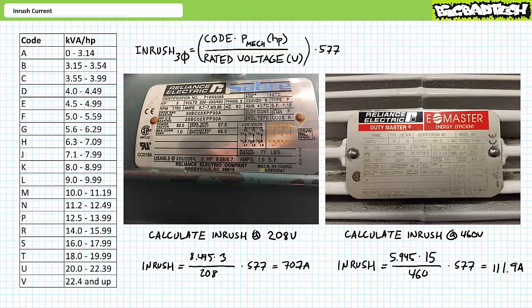Oftentimes generators or off-grid battery-based inverters specify two ratings: a rated current capable of being met on a nearly continuous basis, and a maximum surge current that the system is capable of temporarily meeting. Consider a motor anticipated to draw two amps at rated conditions. Using the six-times shortcut, we might expect an inrush surge of 12 amps. If we used a generator with a rated current of three amps and a permitted maximum surge current of nine amps, it might run the motor but it wouldn't start it without difficulty or without the use of a reduced-voltage starter.